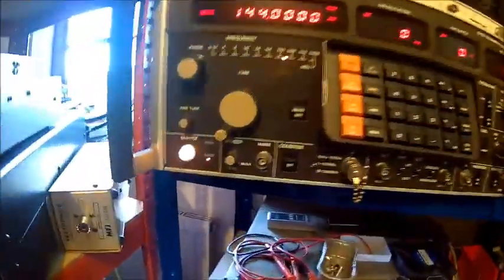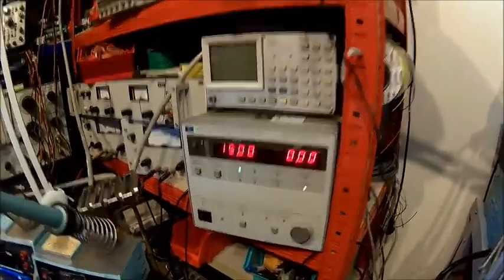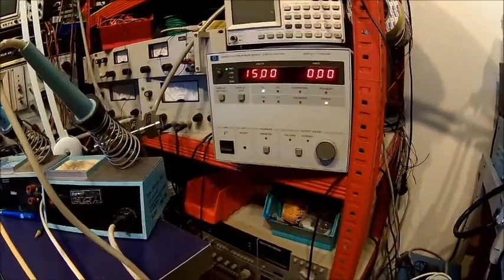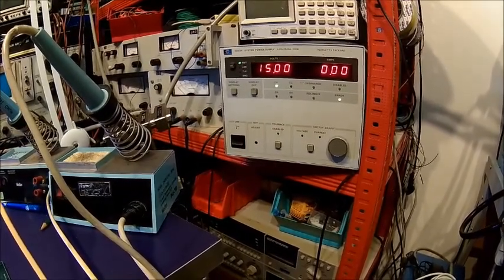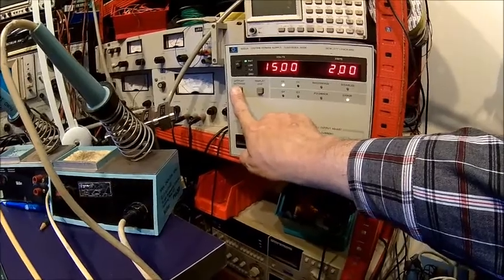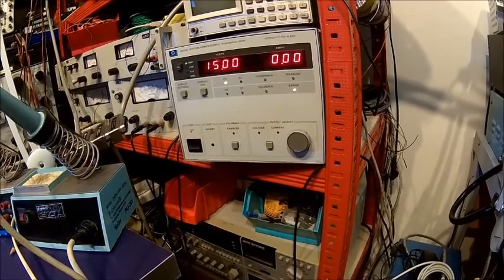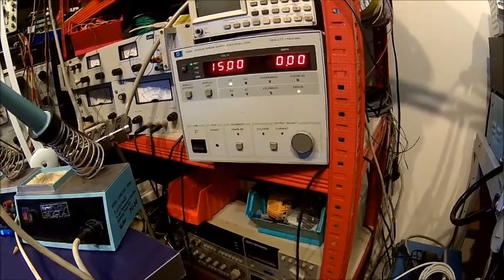So at the moment the instrument is addressed. This isn't addressed. This isn't addressed either, because this is a listen only device. So we're gonna address that meter, that power supply now, which is address number 5. I hit address number 5 and I change the voltage to 10 volts. At the moment our setting is 2 amps at 15 volts, hopefully that's visible. And I send the command to this device to change to 10 volts 1 amp.